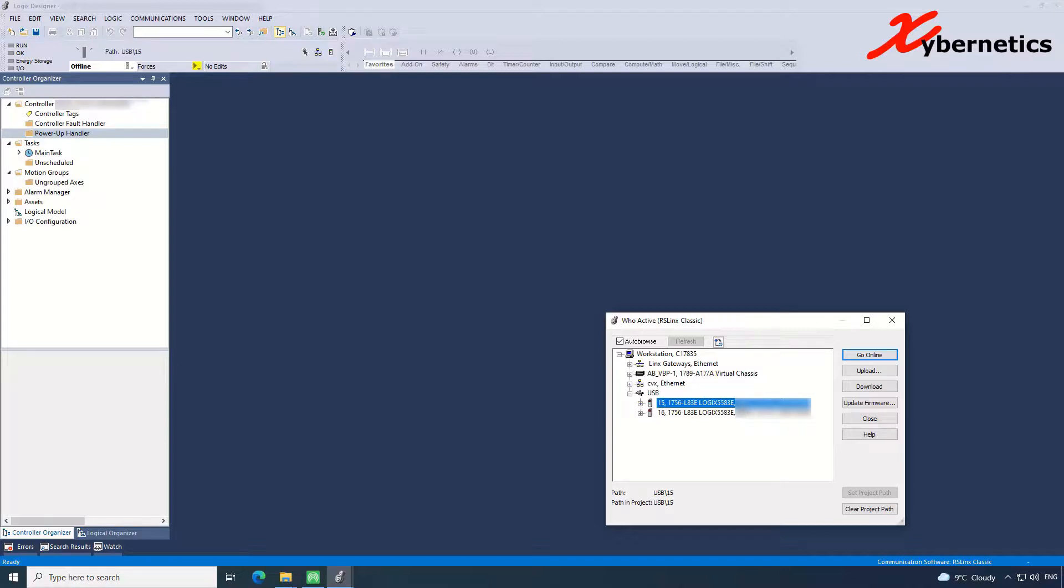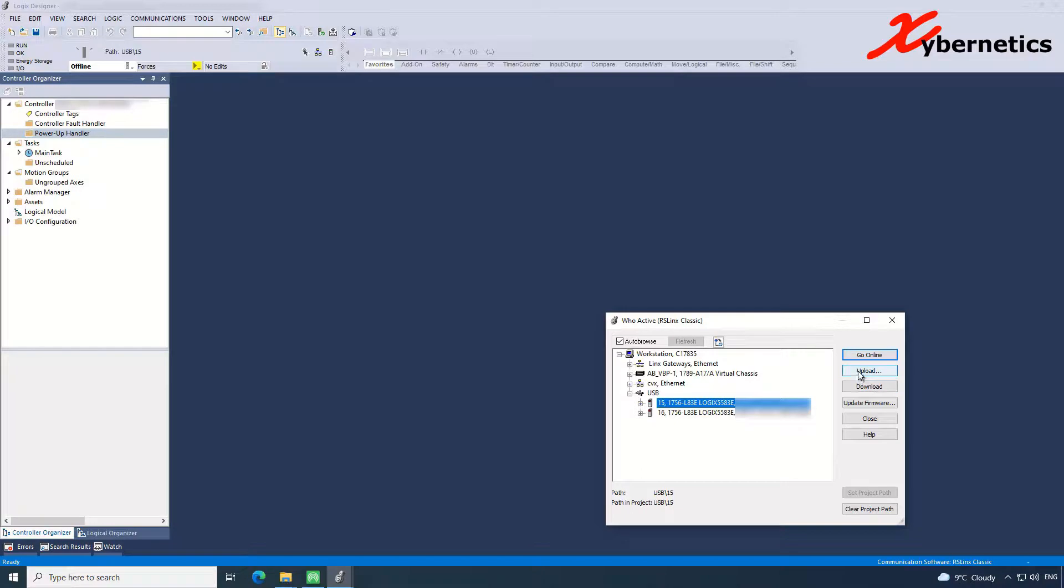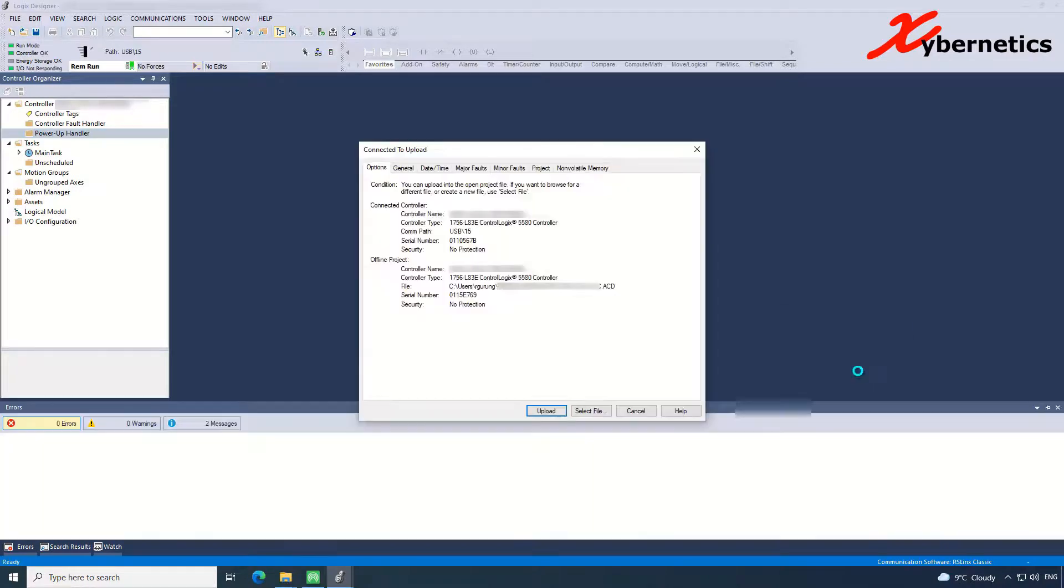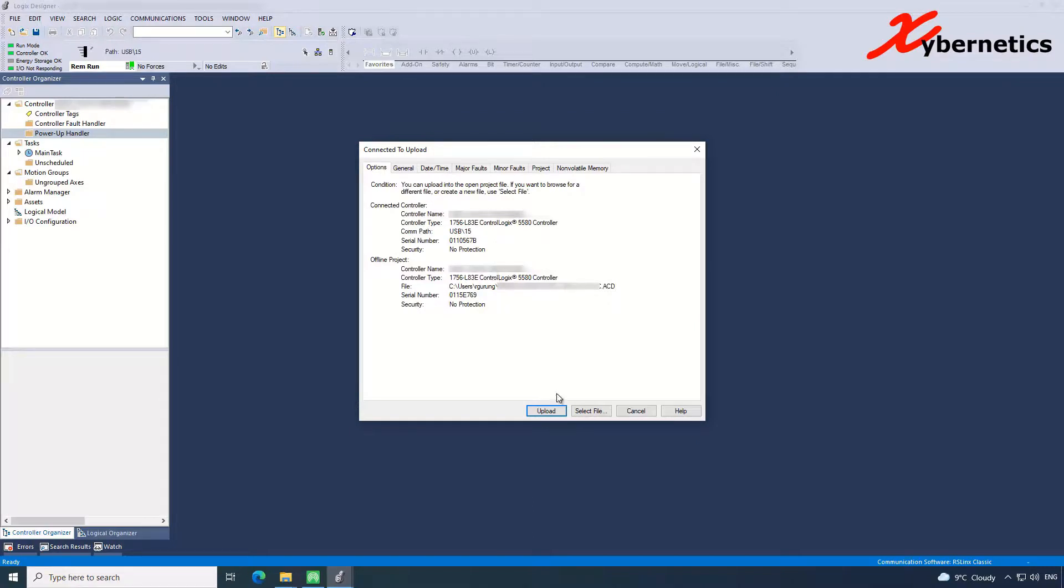So select the PLC and now you'll click upload here. Again, download is to write to the PLC, upload is to read from the PLC. Click upload. After which you'll be presented with this pop-up window here, telling you the connected controller. This is the program that you have, and this is the offline version that you have on your computer. In here, you will say upload.